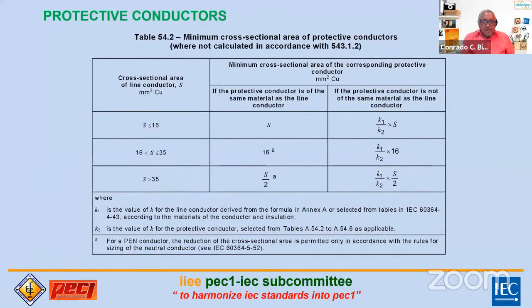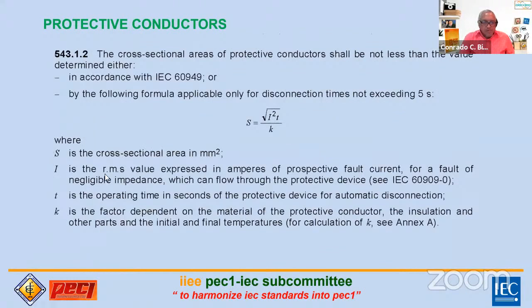So kung ang ginagamit ay mga protective conductors, aside from the requirements, this is the way to calculate the minimum cross section according to the IEC standards, according to this table. So meron siyang mga formula na ginagamit sa protective conductors, where S is the cross-sectional area in square millimeters, I is the RMS value expressed in amperes of the prospective fault current. So meron siyang calculation. And t is the operating time in seconds of the protective device for automatic disconnection. Okay, then k is the factor dependent on the material of the protective conductor, the insulation, and other parts, and the initial and final temperatures. So importante na malaman mo itong k.